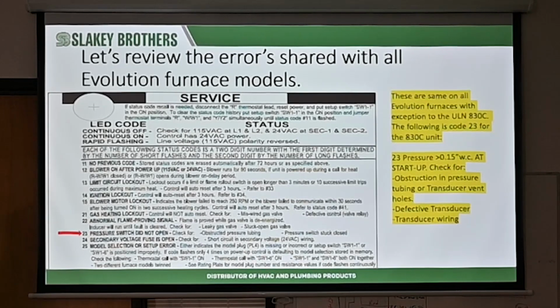If you leave the 6 on because you're doing the testing procedure, then after you're done diagnosing your unit, shut it off. Because if you accidentally leave it on and you ask for heat, it'll give you a fault and nothing will work. So with SW1 number 1 on, or SW1 number 6 on, if you leave them on by accident, it will not work at all, and it'll give you a fault code.